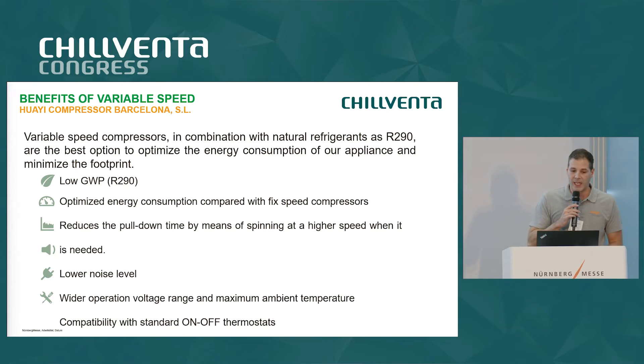Additional benefits include optimized energy consumption compared with a fixed speed compressor. During pull-down, the compressor will run at maximum speed, decreasing pull-down time. Lower noise is also achieved because during a stabilized cycle the compressor is working at lower speed compared with the equivalent fixed speed model, so the noise level is reduced.